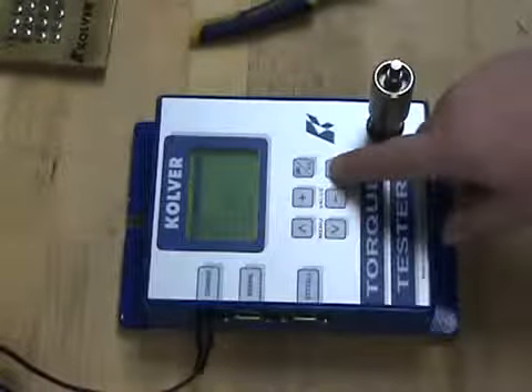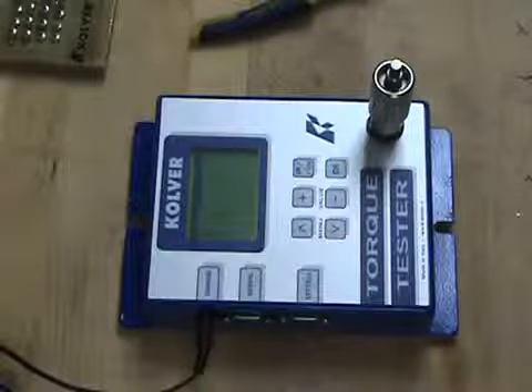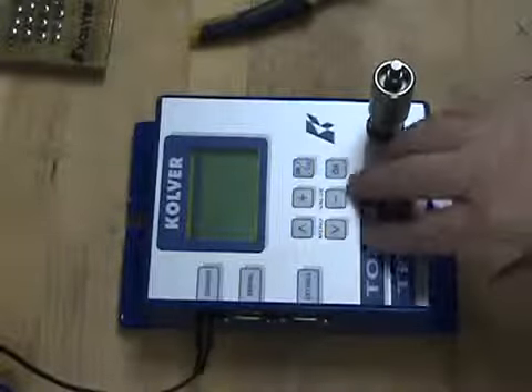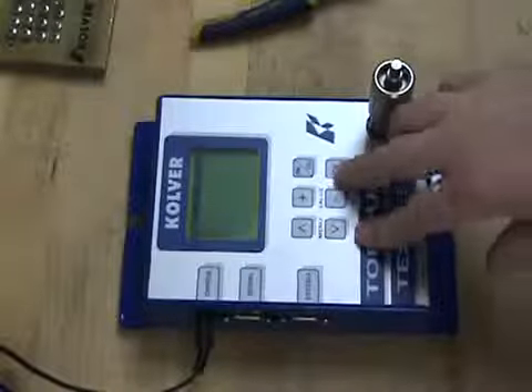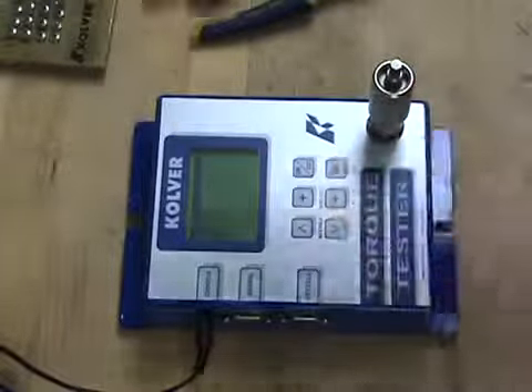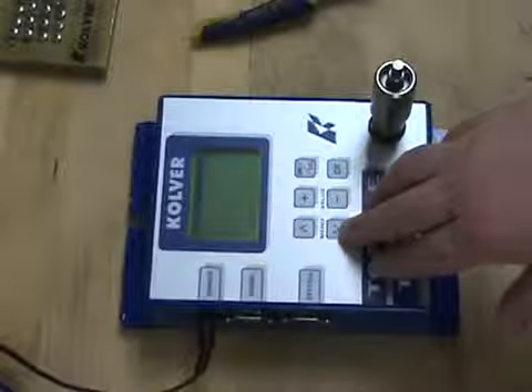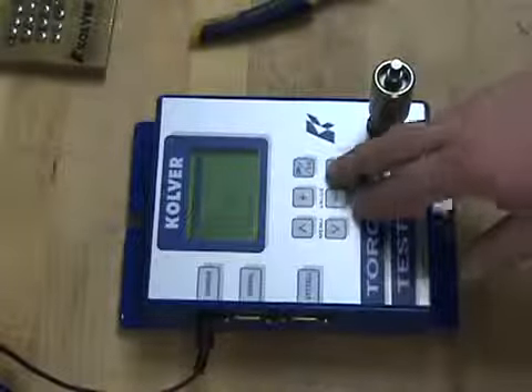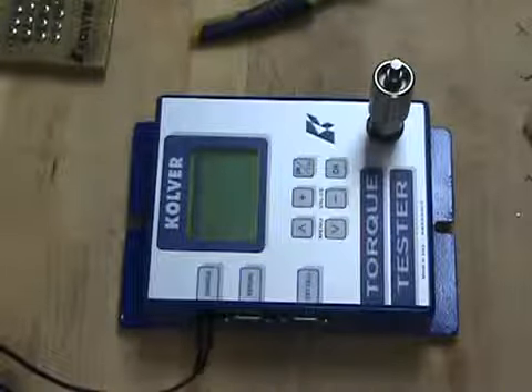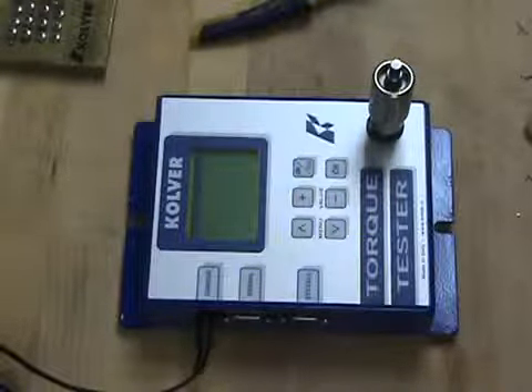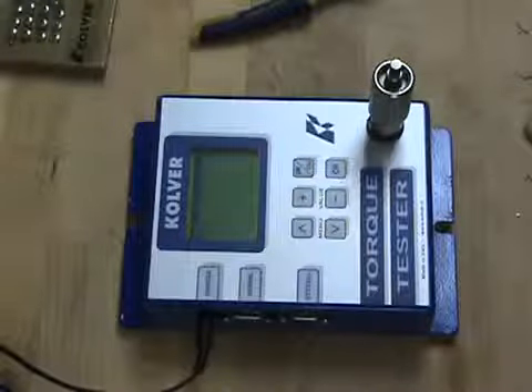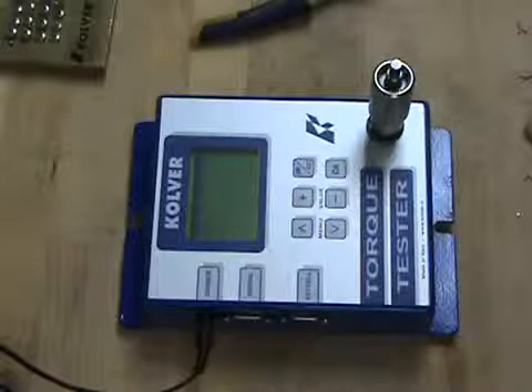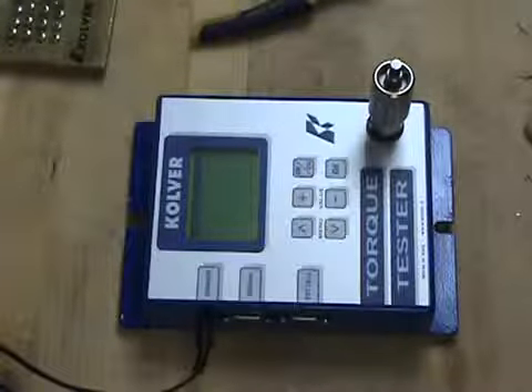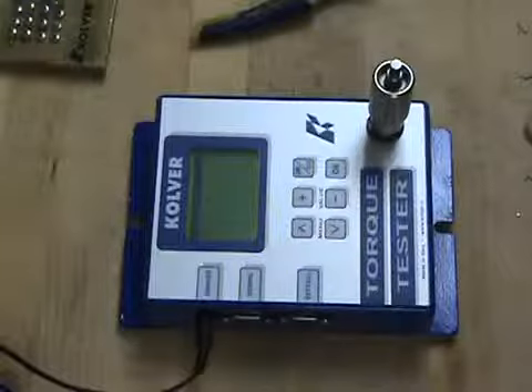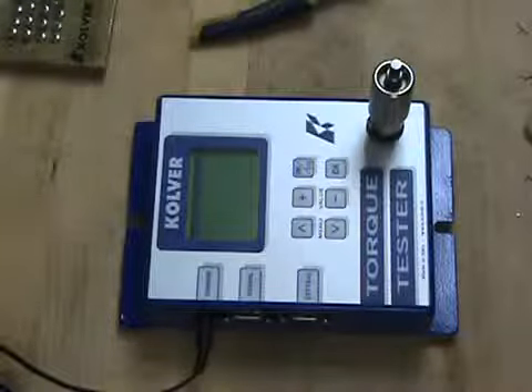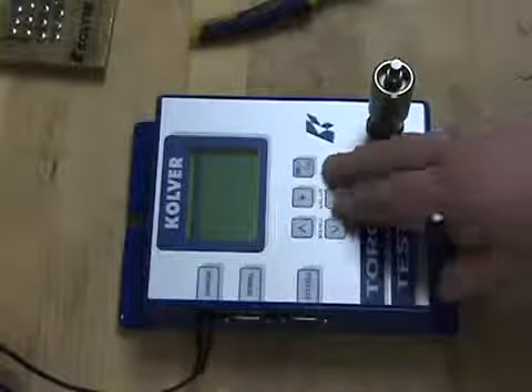We can go into unit. Here we can select Newton meters, Newton centimeters, kilograms per centimeter, or inch pounds. We are currently on inch pounds. You can select OK for your particular unit, and auto reset will allow for a new number to appear each time you do a rundown, so you do not have to press OK or Escape to move on to the next reading. This will do it automatically for you each time, and it's currently set to on.